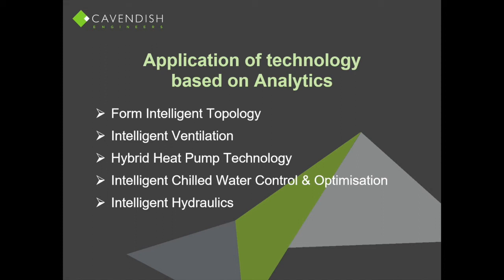Intelligent chilled water control and optimization - this is where we're controlling chillers to be intelligent, so they only load up or unload depending on what they're actually being asked to do. Nearly every chiller in a building sits on its own intelligence right now, programmed in by the manufacturer.